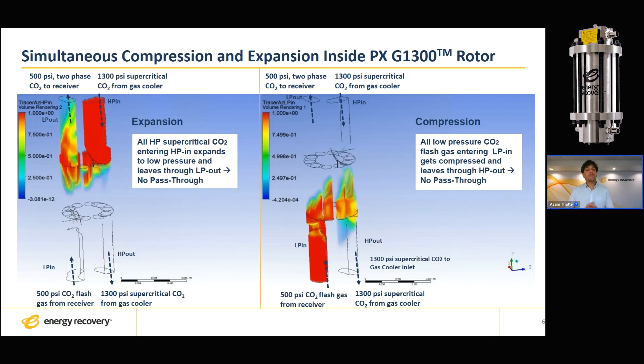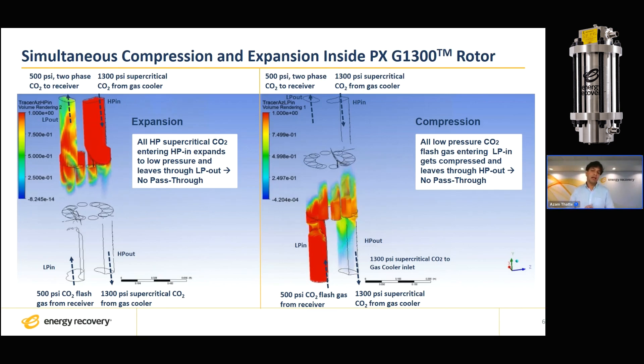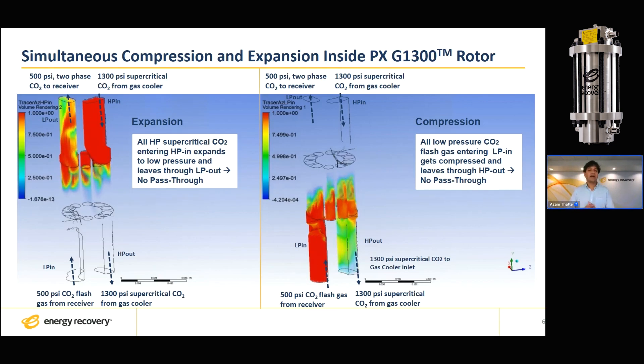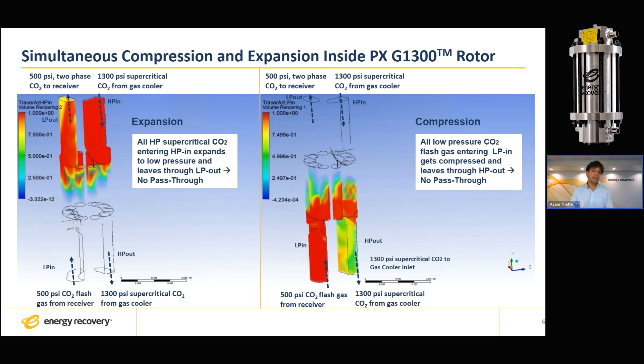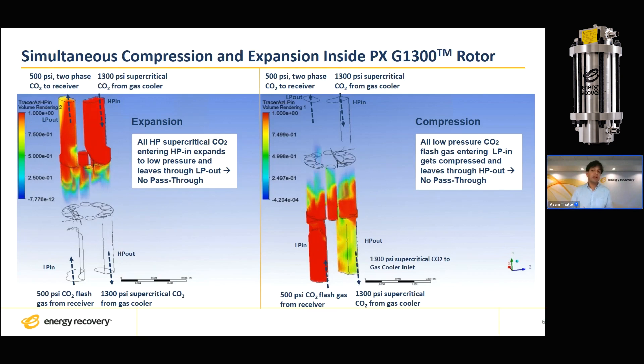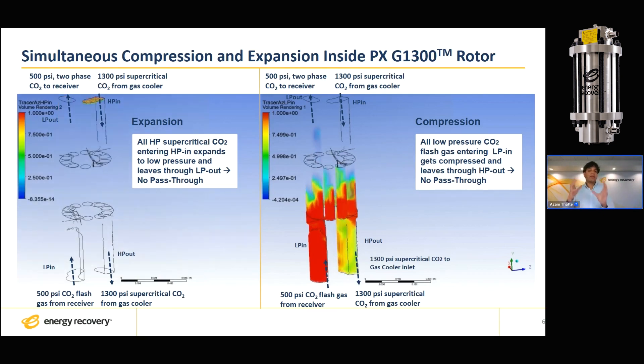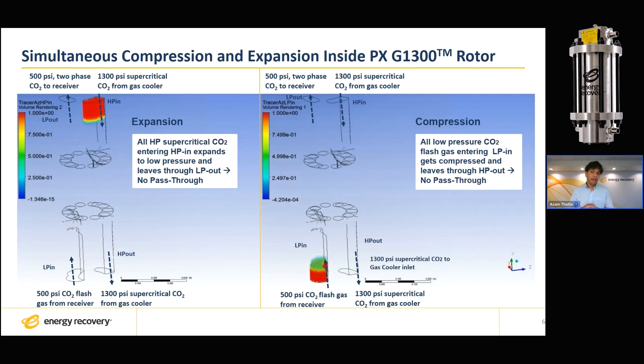If you focus your attention on the right half, what you are seeing is a low-pressure CO2 gas entering the rotating duct of the pressure exchanger. That gas can be anywhere around 550 psi if it's coming from the receiver, or it could be as low as 380 psi if it's directly coming from the evaporator. That low-pressure gas then gets sealed in the rotating duct as the duct continues its rotation.